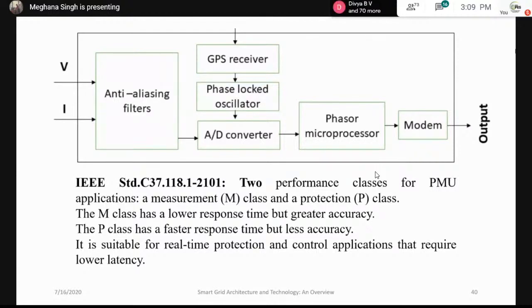The standard is C37.118, 1-2011. There are two classes: M class and P class. M class is for protection and measurement, P class is for protection. M class has lower response time but greater accuracy, while P class has faster response but less accuracy. It depends on what kind of class you need. For real-time production and control requiring low latency, go for P class.